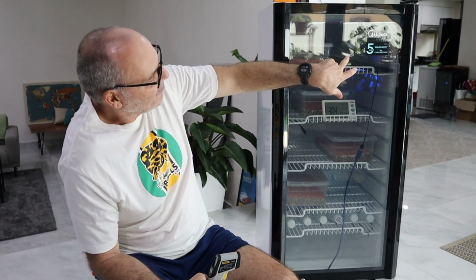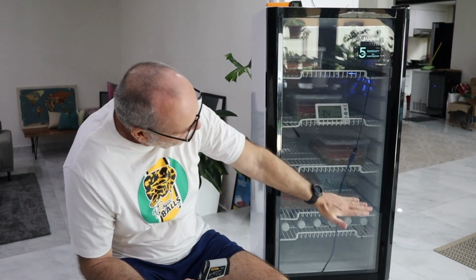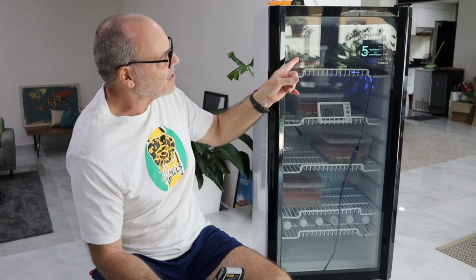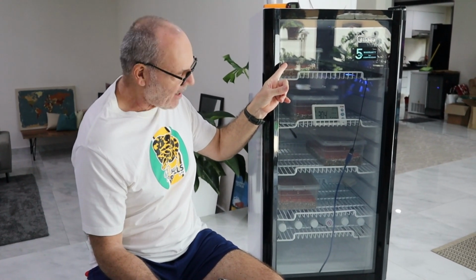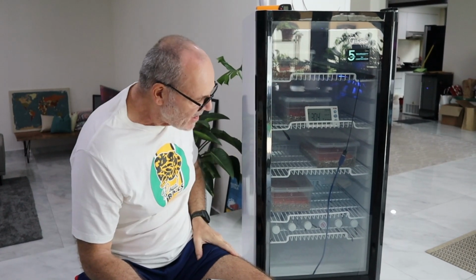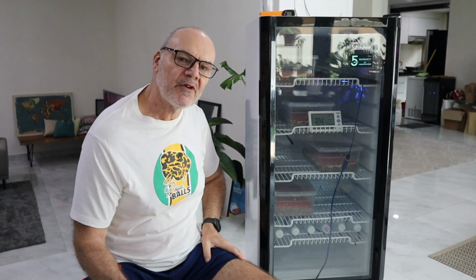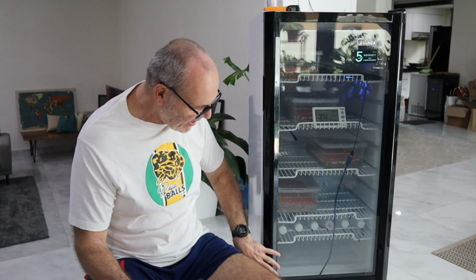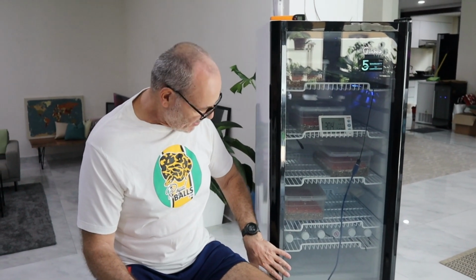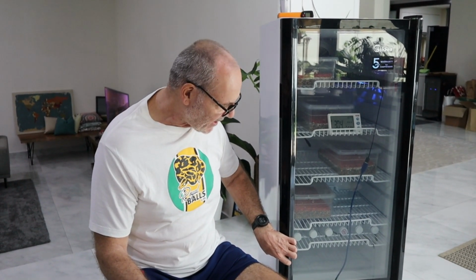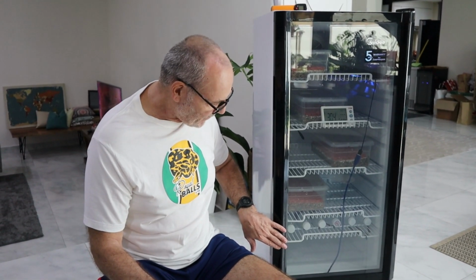I know that if my fan fails, the incubator from this point down is still giving me a very stable temperature. It's only the top that's the dead zone. So I've learned that about my incubator, and what that does is give me the confidence that this incubator is now running stable enough, and that I don't need to mess with it now in order to get it running satisfactorily. I have the confidence in this incubator that it is going to do the job for me, and I don't need to make drastic changes.